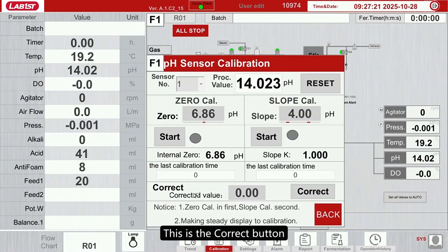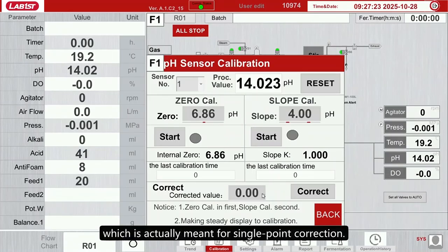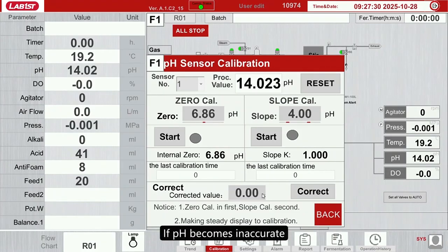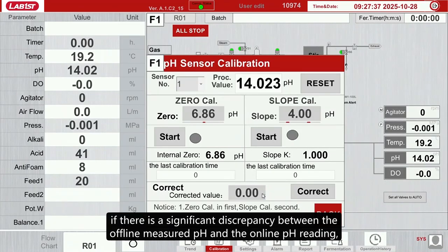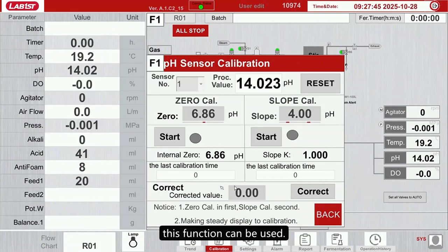This is the correct button, which is actually meant for single-point correction. For example, during the cultivation process, if pH becomes inaccurate. After sampling, if there is a significant discrepancy between the offline measured pH and the online pH reading, this function can be used, as the pH electrode would become inaccurate. This will correct it to be more accurate.